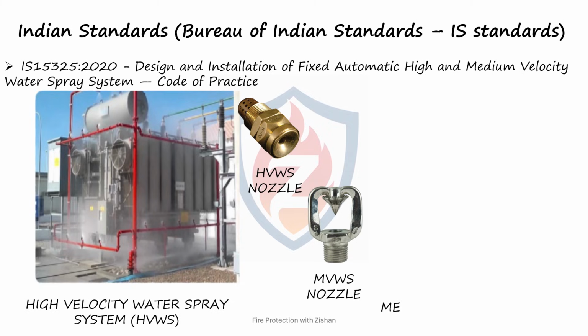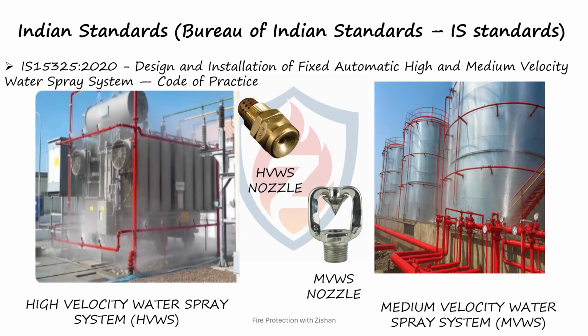On the right, we can see a medium-velocity water spray system, or MVWS, installed around storage tanks. These systems are primarily designed to cool equipment and structures exposed to fire, preventing heat buildup and reducing the risk of fire spread. They form a protective water curtain around the equipment, helping to maintain structural integrity during a fire emergency. The key difference between the two systems is their application.